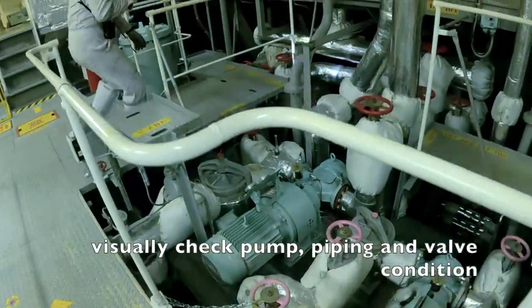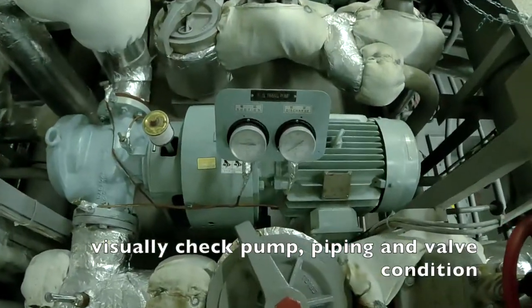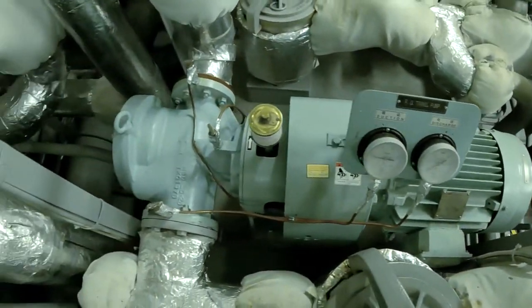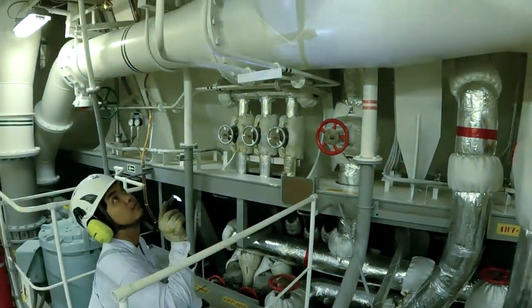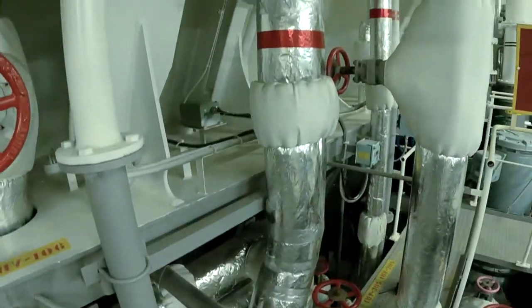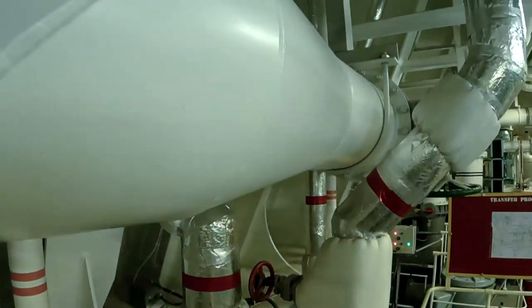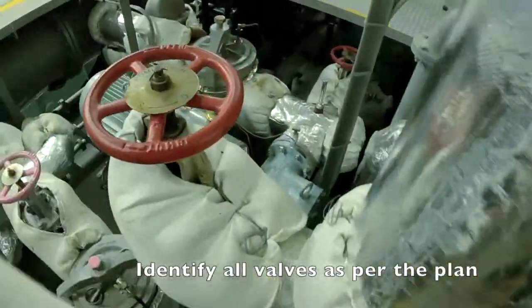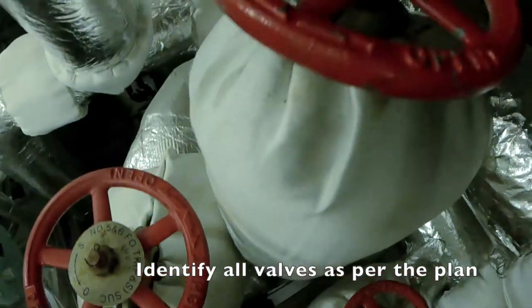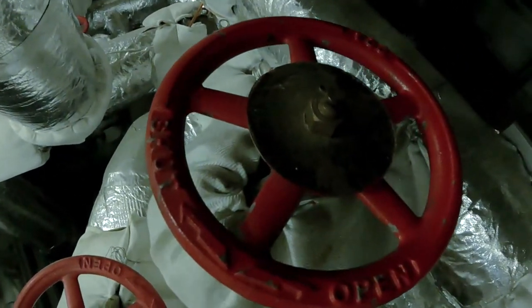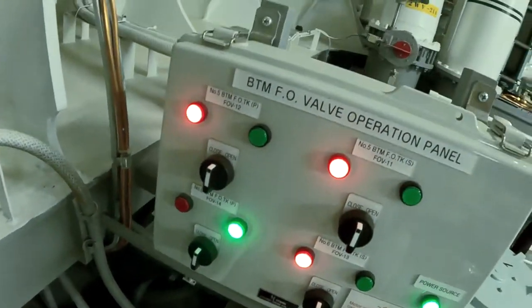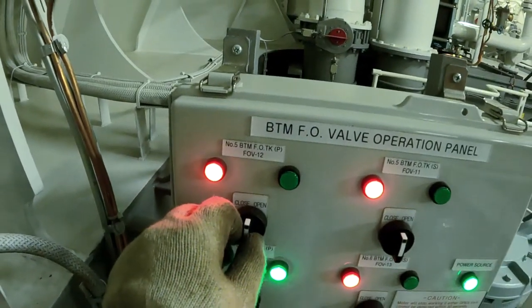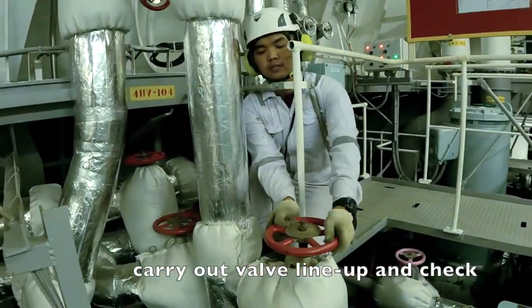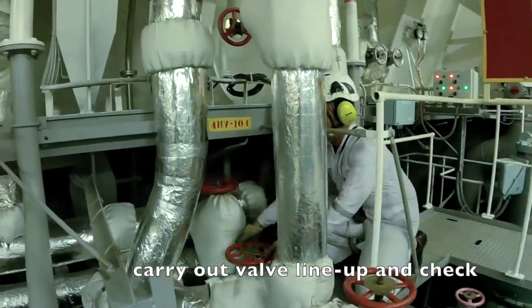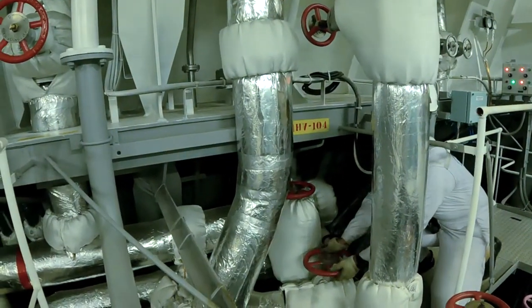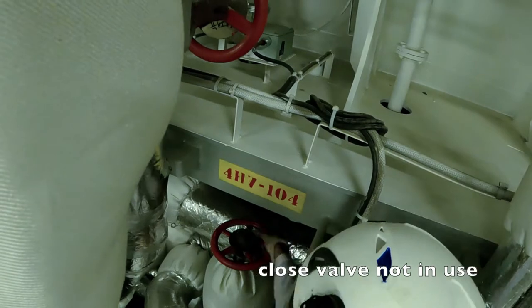Visually check pump, piping, and valve conditions. Identify all valves as per the plan. Carry out valve line up and always double check. Close other valves that are not in use.